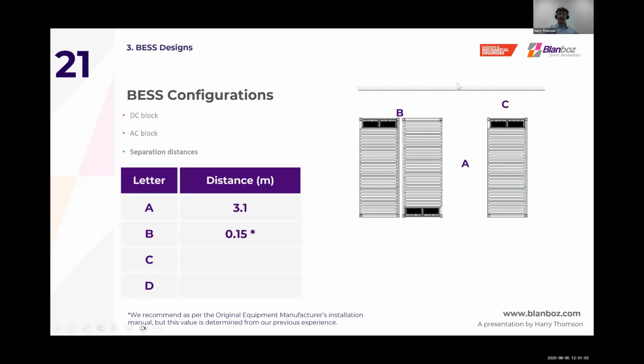We then have C, which is the distance between a container and an obstacle, such as a wall or another container. Again, we recommend following the OEM's installation guides, but in our experience, this has been around 2.5 meters. This is to allow for cool, clean air to get into the HVAC and properly cool down the system, especially during heavy cycling.